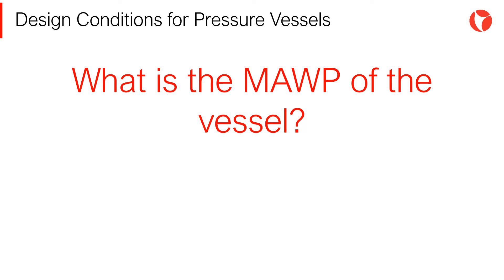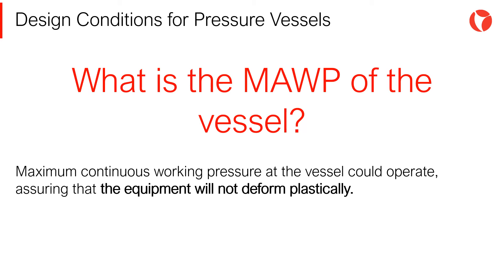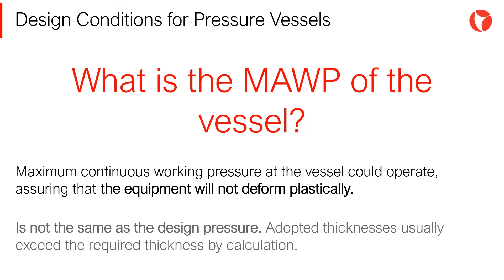The MAWP, or maximum allowable working pressure, is the maximum continuous working pressure at which the vessel could operate, assuring that the equipment will not deform plastically. The MAWP is not the same as the design pressure. Adopted thicknesses usually exceed the required thickness by calculation, and this excess is what generates the pressure jump up to the MAWP.